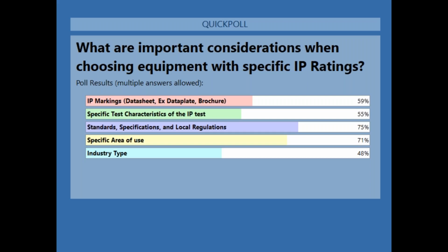Designers shall block the use of equipment that is not the correct IP rating as per their facility's end user specifications. If the manufacturer or the testing laboratory doesn't test to the correct IP rating or doesn't mark their own documentation correctly, an EPC, a purchaser, may not purchase their equipment.